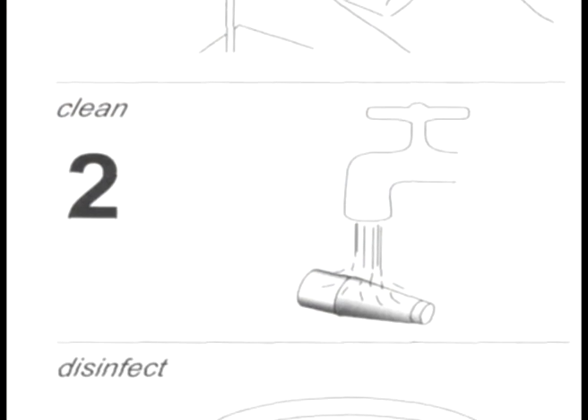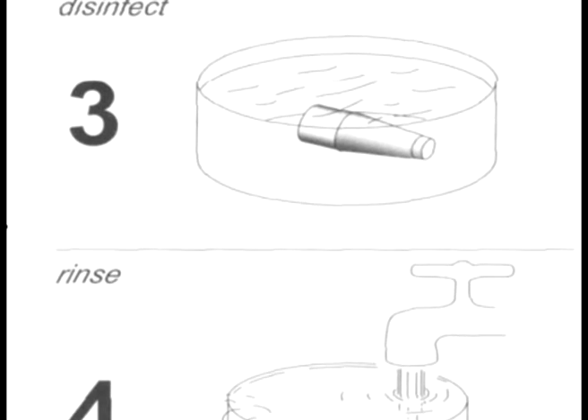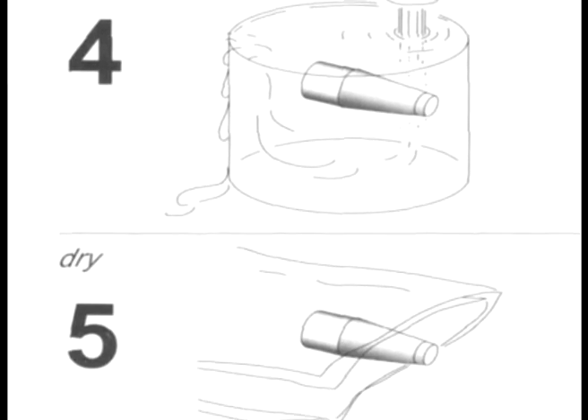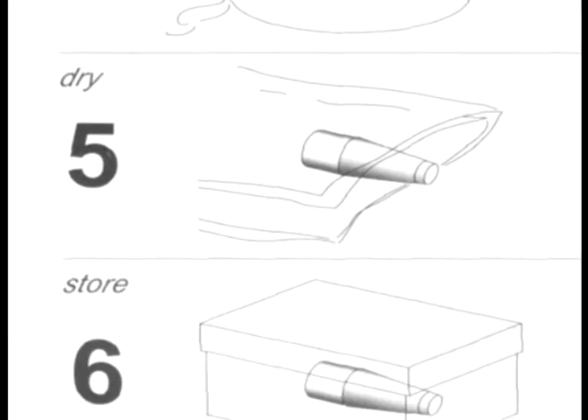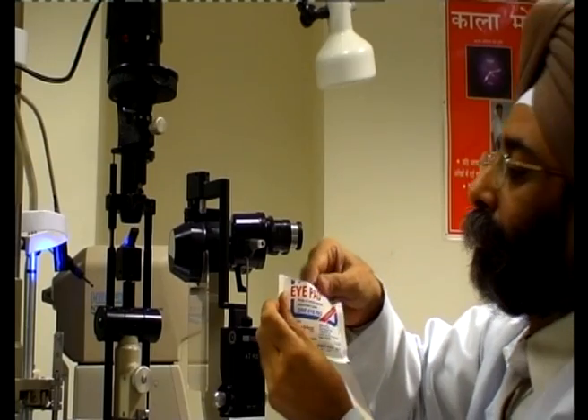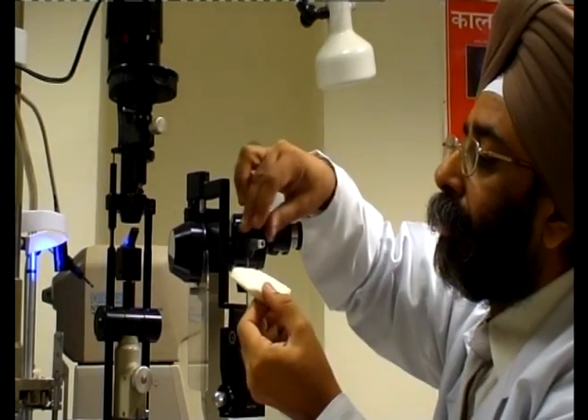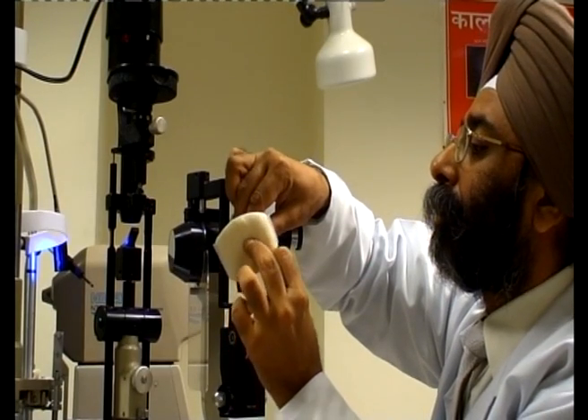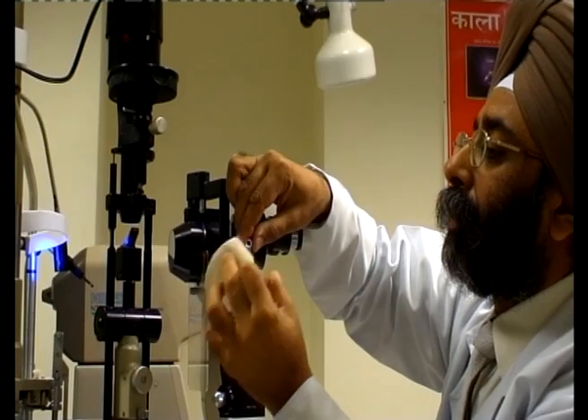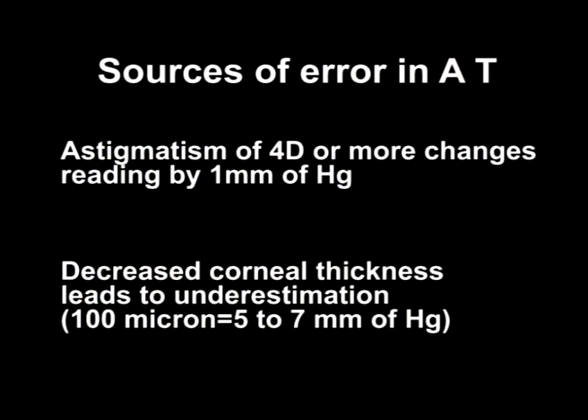Disinfection of the prism is best done by home bleach, sodium hypochlorite, 3% hydrogen peroxide, mild soap, or proprietary disinfectants recommended by manufacturers. For cleaning in between cases, using hydrogen peroxide, dilute bleach, or simply distilled water are the most practical. One should make sure that the prism tip is dried before use to avoid getting excessively broad mires.